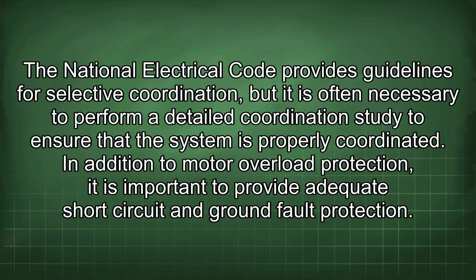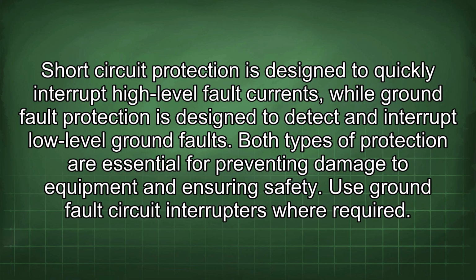In addition to motor overload protection, it is important to provide adequate short circuit and ground fault protection. Short circuit protection is designed to quickly interrupt high-level fault currents, while ground fault protection is designed to detect and interrupt low-level ground faults. Both types of protection are essential for preventing damage to equipment and ensuring safety.